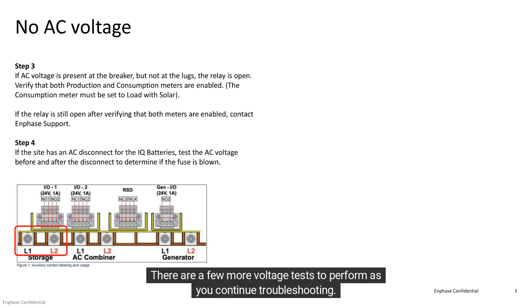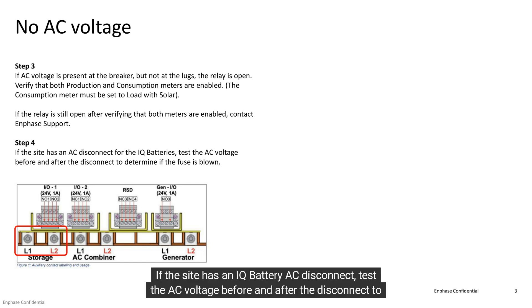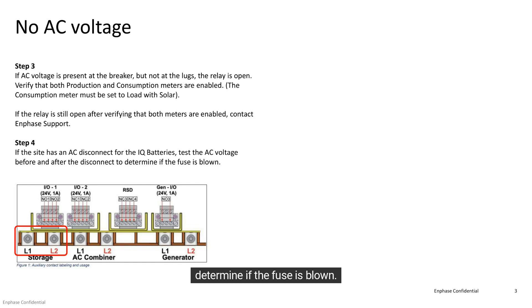There are a few more voltage tests to perform as you continue troubleshooting. If the site has an IQ Battery AC disconnect, test the AC voltage before and after the disconnect to determine if the fuse is blown.